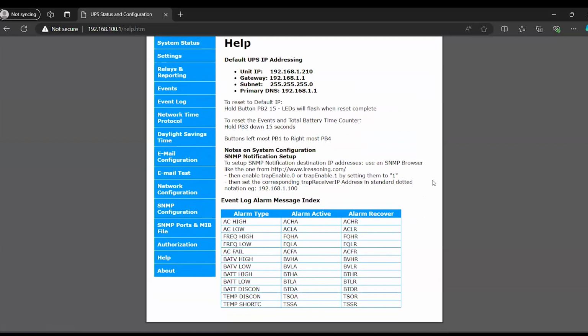It'll give you some notes on configuring the SNMP for the unit, and at the bottom you have that table, just like in the manual, showing exactly what each of those alarm codes mean. For example, at the top you have the AC high alarm. If your AC input was too high, you would see ACHA when it detects that state, and when it recovers and the alarm goes away, you would see ACHR instead.